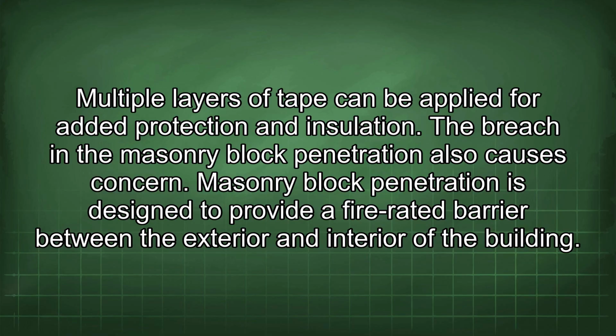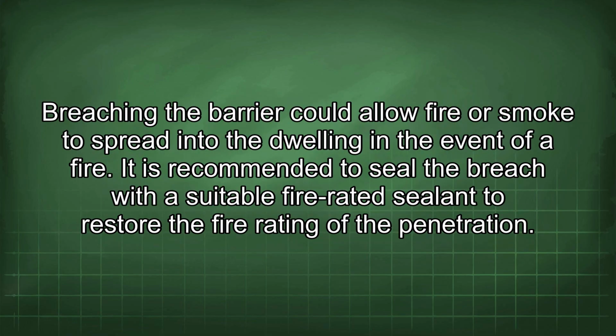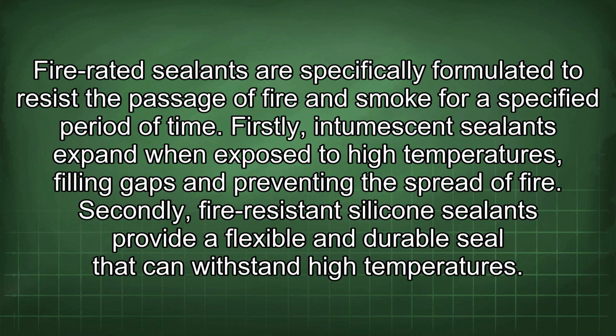The breach in the masonry block penetration also causes concern. Masonry block penetration is designed to provide a fire-rated barrier between the exterior and interior of the building. Breaching the barrier could allow fire or smoke to spread into the dwelling in the event of a fire. It is recommended to seal the breach with a suitable fire-rated sealant to restore the fire rating of the penetration. Fire-rated sealants are specifically formulated to resist the passage of fire and smoke for a specified period of time.